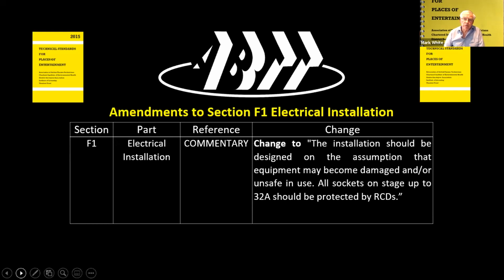Now, the issue with RCDs, particularly on 32 amp supplies, is that they're good for 30 milliamps, which means that you can very easily overload these circuits, even though they're 32 amps in total. We are, in fact, still measuring fairly low earth leakage currents. Now, earth leakage currents are everywhere today in theatre equipment. Moving lights, for example, video walls, and just about everything that we plug into our electrical supply these days.